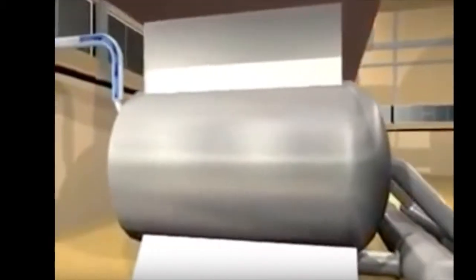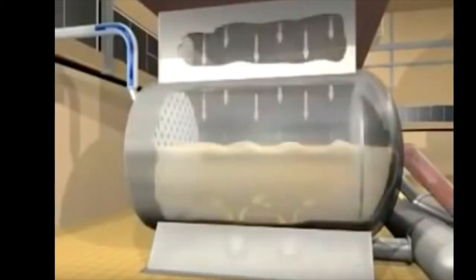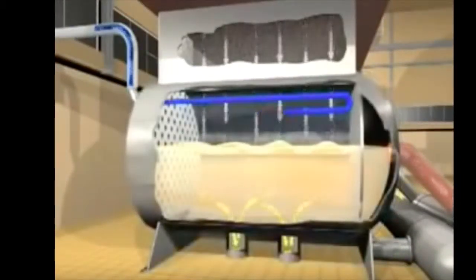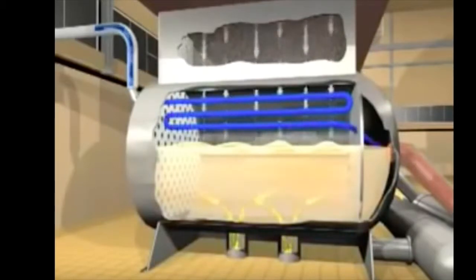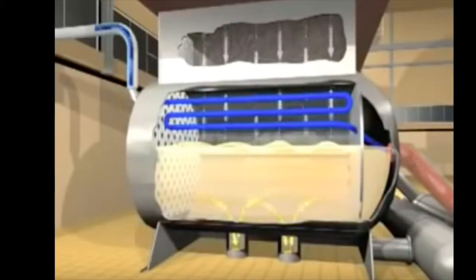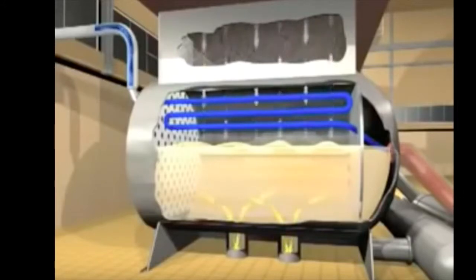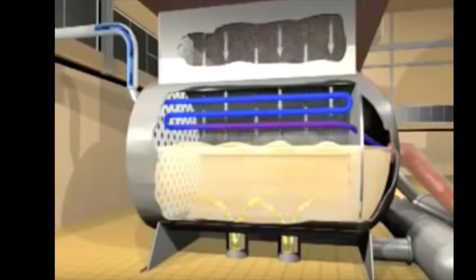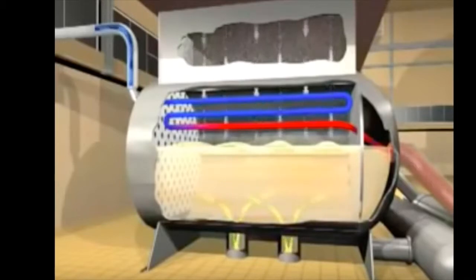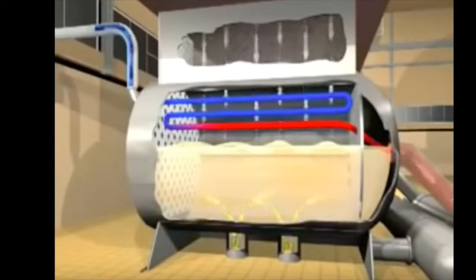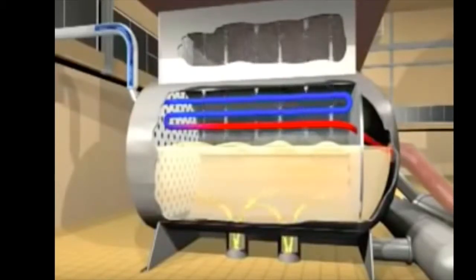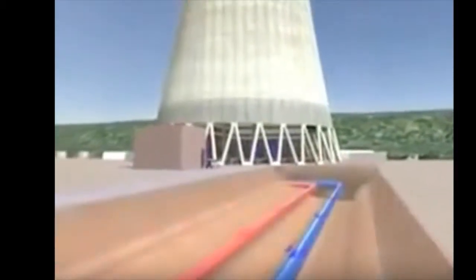Water reuse and condenser. After the steam has been used to create electricity, it is exhausted from the turbine and sent to a condenser to be changed back into water. Inside the condenser, steam passes over the outside of pipes filled with cooled water from the cooling towers. The steam condenses to water and returns to the boiler to repeat the steam generating process over again. As the steam condenses, the cool water inside the condenser pipes becomes warm from the heat of the steam, so it is sent to a cooling tower.